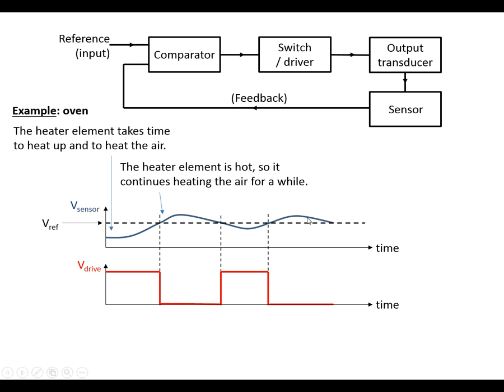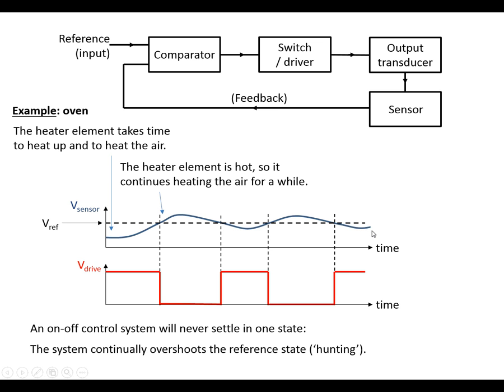And it continues. Again, it's going to overshoot because the heater is still pumping out heat. And so on. And we can see from this one that the on-off control system, it never settles at exactly the reference. It always oscillates around. And this is what we call hunting.